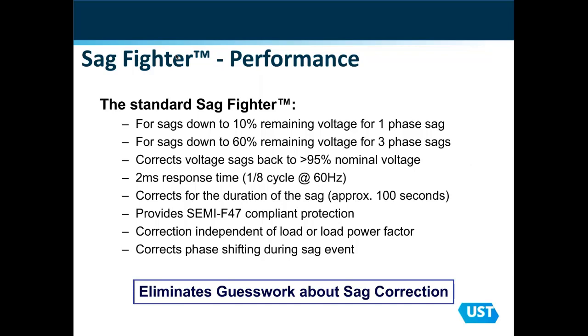All the corrections are back to 95% of nominal, plus or minus 5%. Again, as I mentioned before, 2ms response time. It is a SEMI F47 compliant device. That's important for people in the semiconductor industry. And it will correct for phase shifting and is independent of load or power factor.